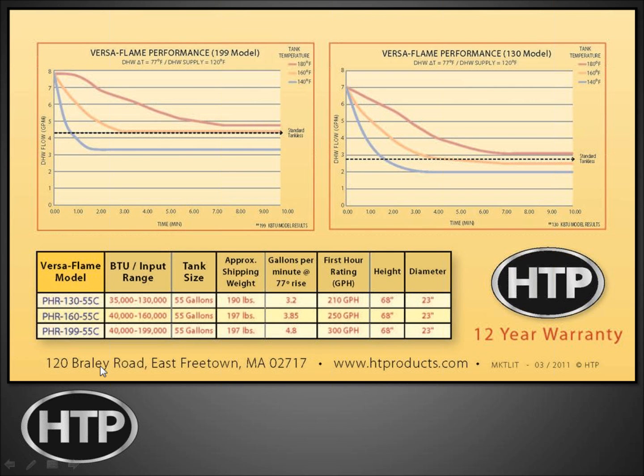This gives you that flow chart. This is a nice flow chart to use. You can see here we have a red line, a yellow line, and a blue line. And what we're showing you is that by raising the minimum tank temperature, we can actually produce more domestic hot water. And you can see this area here, which I was talking about. At 180 degrees, we can give you a very high peak draw, and we don't start flattening out until we're up to about 6 to 7 minutes of draw. So that gives you a lot of power for quite a bit of time, where a tankless is a straight line number. And it will fluctuate based on pressures, and it will fluctuate based on temperatures. So we have a real advantage here in the operation of this system.